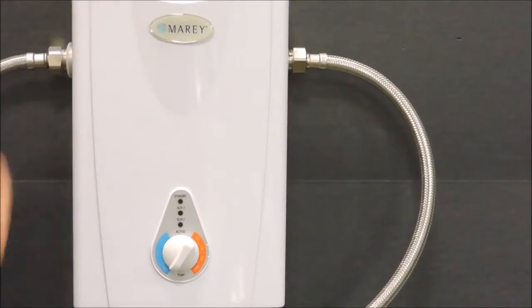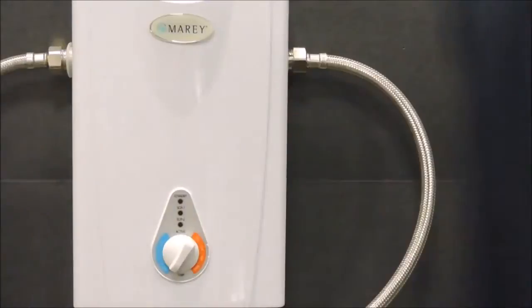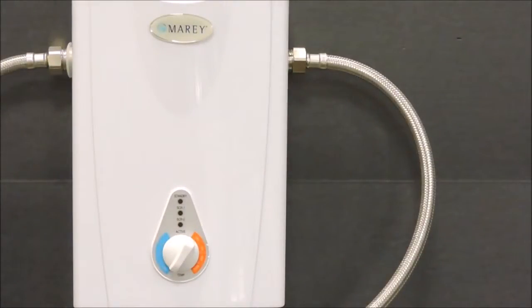Never use PVC on the hot water outlet. Instead, use CPVC or other heat-rated materials. In this case, I am using heat-rated steel-braided hose for both the inlet and the outlet.